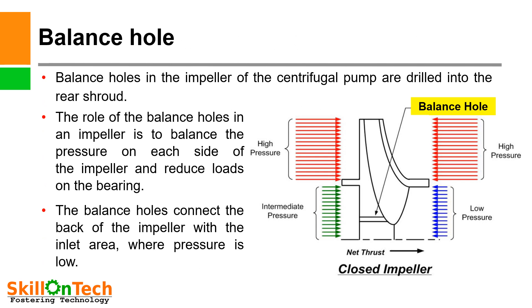Balance hole: You can see a picture of an impeller where a balance hole is shown. By providing a balance hole in the impeller, the axial thrust is balanced. Balance holes in the impeller of a centrifugal pump are drilled into the rear shroud. The role of the balance hole is to balance the pressure on each side of the impeller and reduce the load on the bearing. There are two high pressure regions visible; at an intermediate region the pressure is lower, and the suction side has low pressure. By providing a balance hole, the net axial thrust can be reduced. The balance hole connects the back of the impeller with the inlet area where pressure is low.